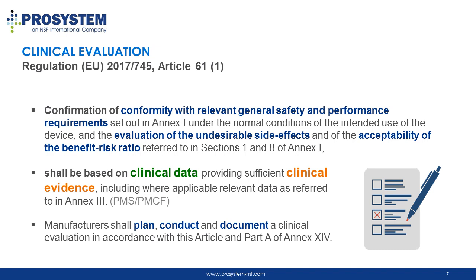Article 61 of the regulation defines clinical evaluation. The aims of the clinical evaluation are to confirm the conformity of a medical device with relevant general safety and performance requirements, as well as to evaluate the undesirable side effects and the acceptability of the benefit-risk ratio.